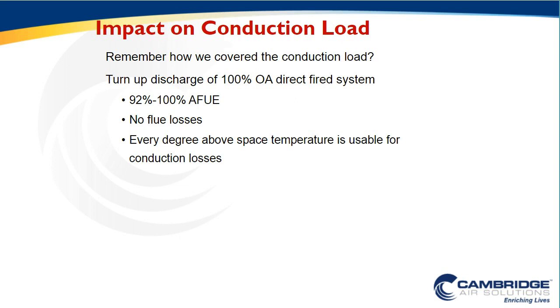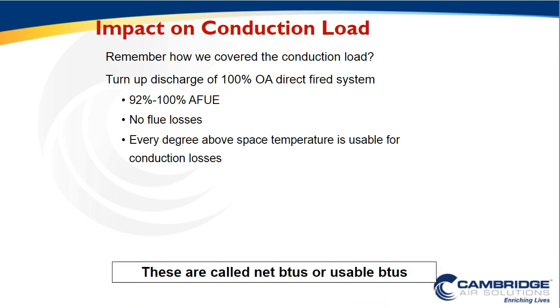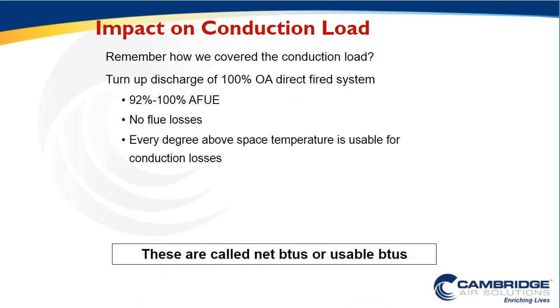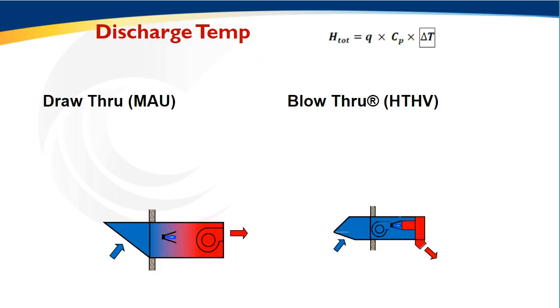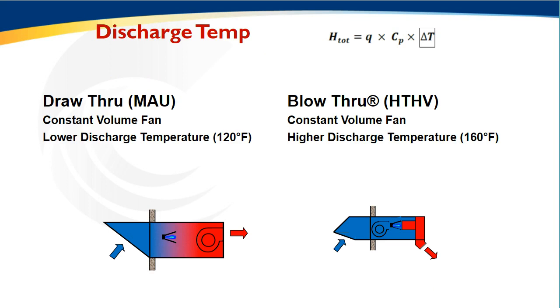They're both going to have 92% thermal efficiency with no flue losses. But what about our ability to deliver net BTUs or usable BTUs to counteract any conductive loss? So now we're going to change the delta T variable slightly. We have our same discharge temperatures, 120 and 160. However, instead of comparing the full temperature rise, I really just want to look at the difference above space temperature.